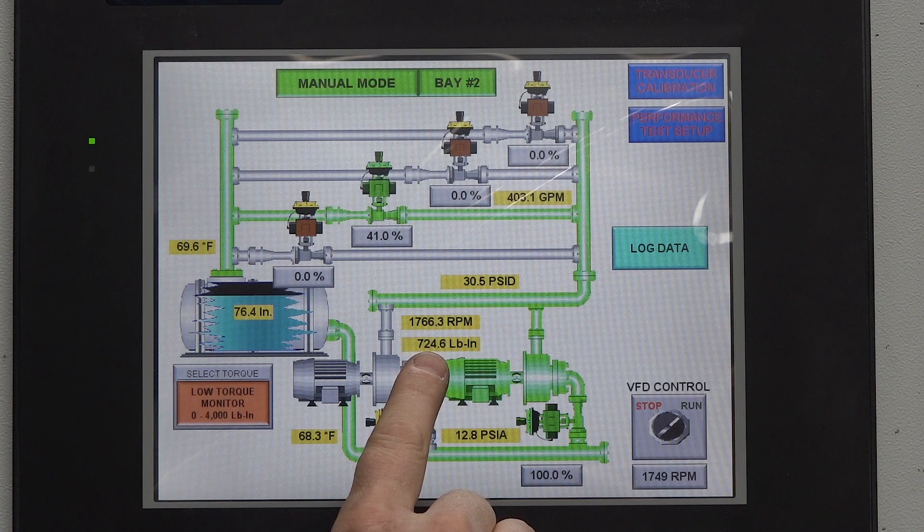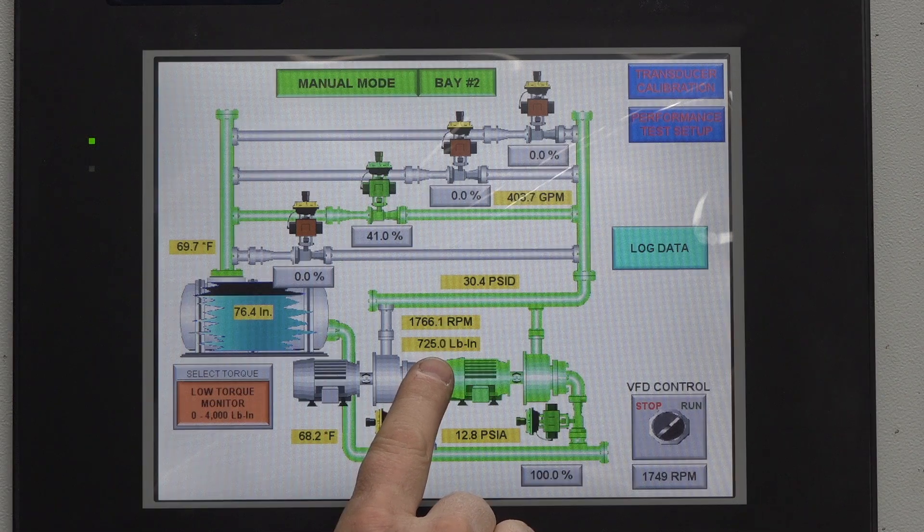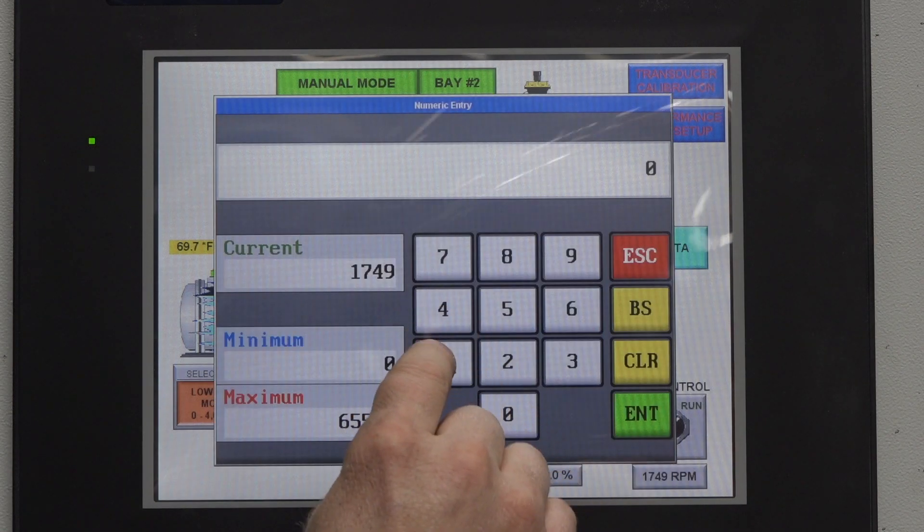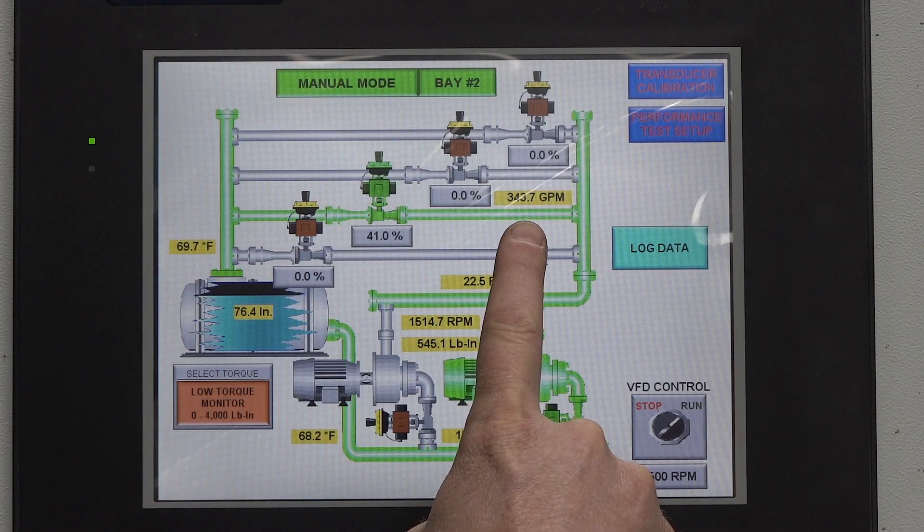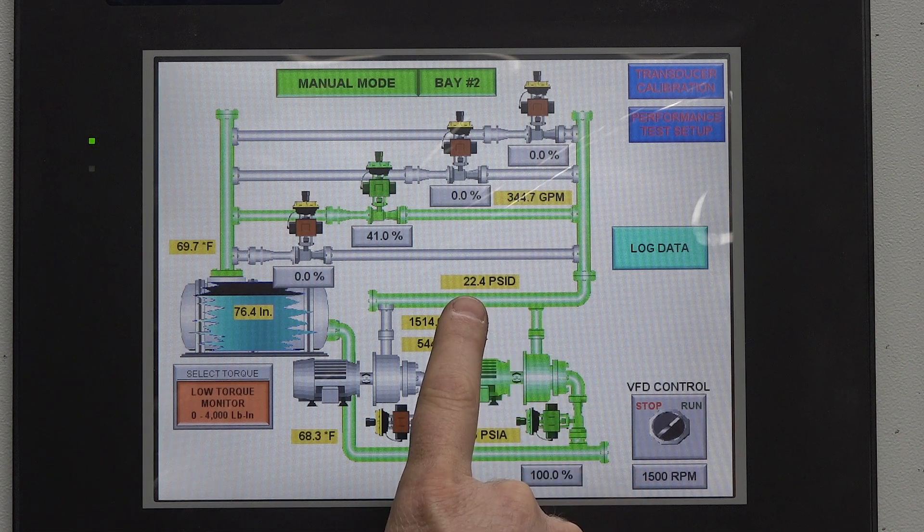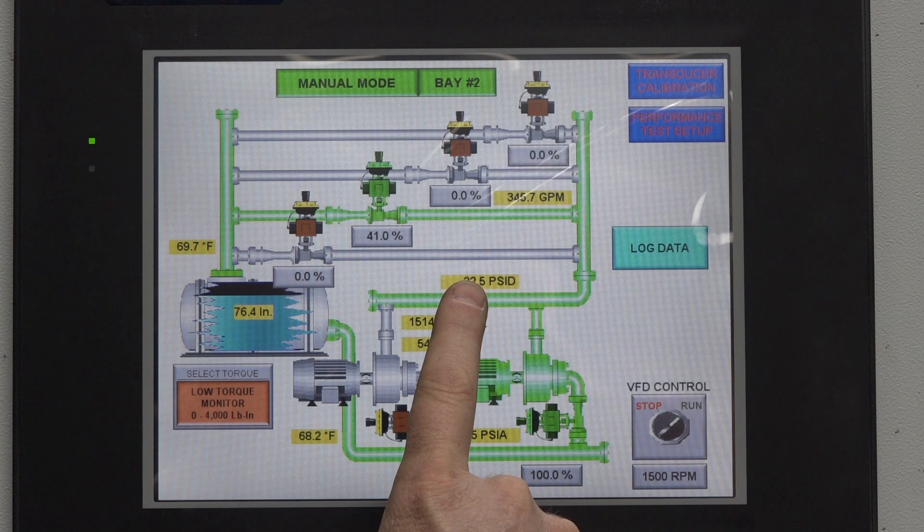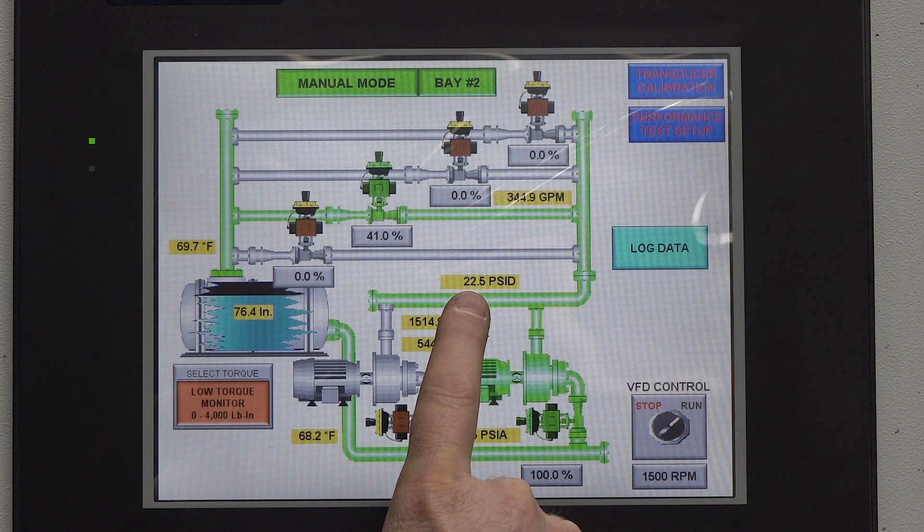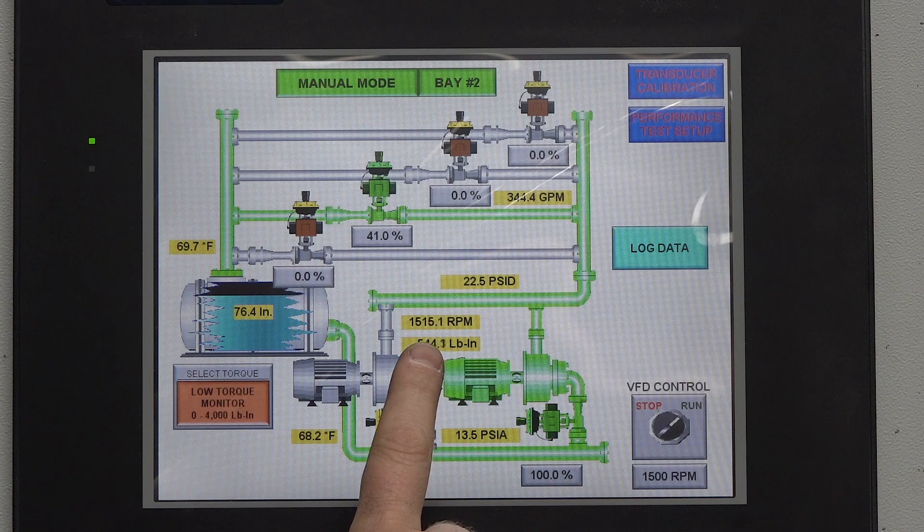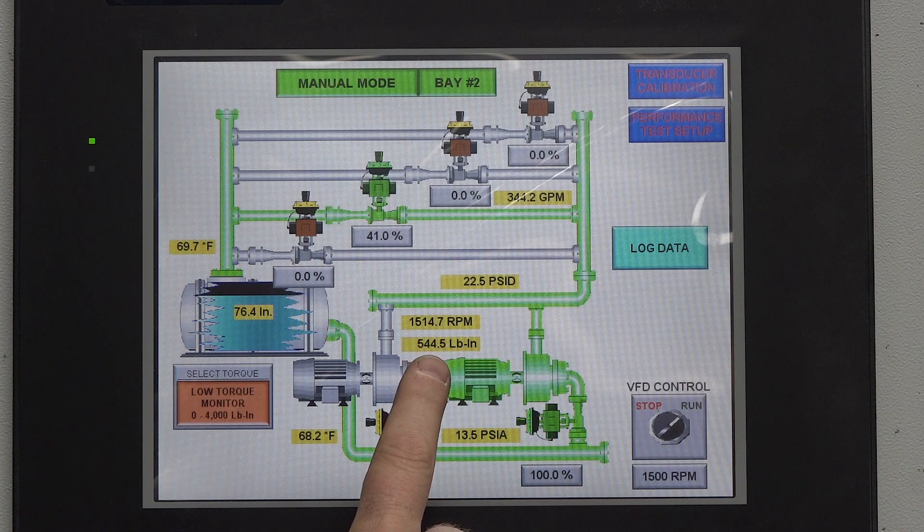We're now going to change the pump speed and we're going to drop it to 1500 rpm. Here the flow rate is now 343 gallons per minute. The differential pressure is 22.5 psi or 50.9 feet. And our horsepower is calculated at 13.1.